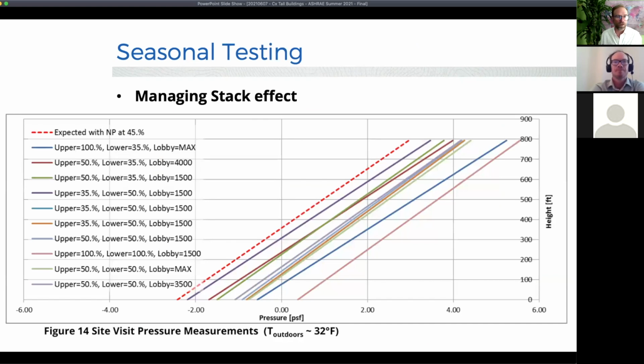In this example of the project in Chicago, we wanted to understand our ability to manage the stack effect with the mechanical systems. Once the building was fully enclosed and partially occupied, we were able to start simulating the building with load and under a sealed environment. So we had 3 different zones. We had a lobby makeup air unit. We had one that served the lower and middle portion of the building as far as ventilation makeup. And then we also had a ventilation makeup air unit at the top portion of the building.